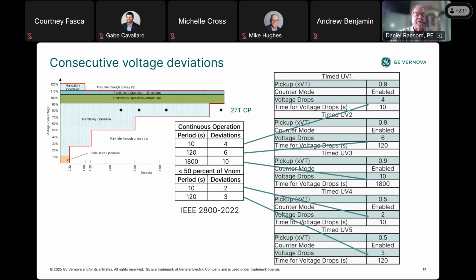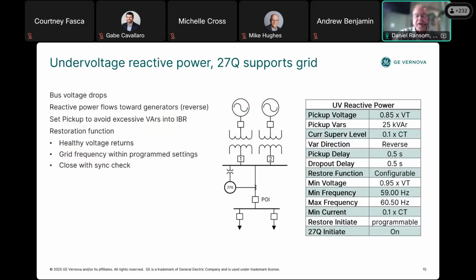If the voltage drops are greater than 50%, as you can see here, in 10 seconds, you can have 4 and then you're allowed to trip. If the voltage drops are more severe, under 50% of VNOM, then after 2, the 27T element operates and signals the controller. In recent standards and grid codes, the DER unit feeding into the transmission system must support the power system voltage upon a network failure. And the purpose of this is to keep stability in the system.